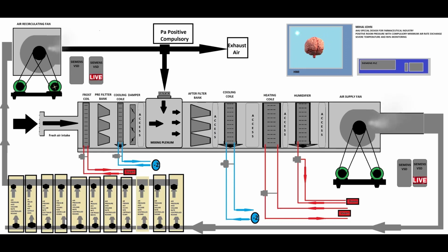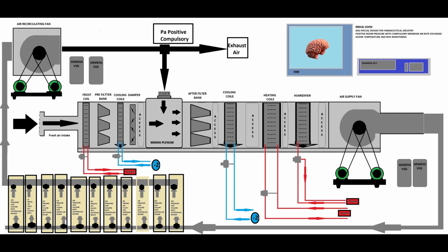The only bad situation which can affect you is if you have a massive mechanical failure on the fan bearings, because even if you have two motors, there's nothing you can do, and then you will lose the process, and this is bad luck. As I said, the system is far from perfect, but at this stage it is what we've got, and that's it. We don't have anything else. We have to deal with what we have.